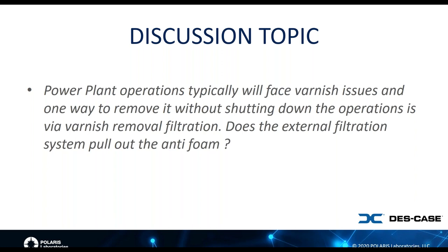If we're talking about a gear oil, yes, caution needs to be there for removing anti-foam. But for turbine oil, if that's the question here, I would not be concerned with any filtration, whether it's a varnish removal system or otherwise, pulling out the anti-foam. I could envision some weird chemistry that would do it, but under normal circumstances, I don't think you would have any real concerns there.